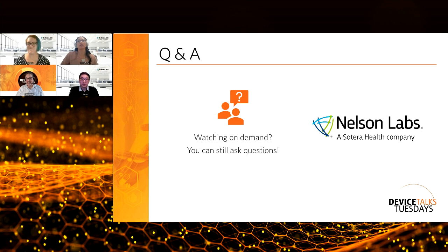So the answer to this question is biocompatibility testing remains valid as long as you don't change anything about your device. So it's really in what changes. As we have developed better science and more refined test procedures, that doesn't mean necessarily there's now this newly established risk for the patient that's going to be exposed to a device that's been on the market for 20 years that we know is safe. But if we did biocompatibility testing 10 years ago, and we've done maybe 5 or 6 or 7 or 10 or 20 small changes that we said, oh, this doesn't impact biocompatibility, I would bet you probably have a whole new device that's not been assessed for biocompatibility.